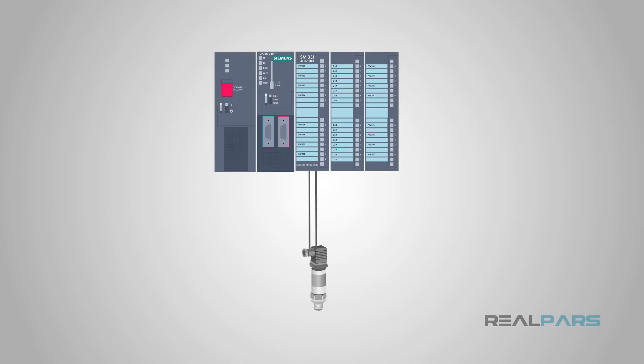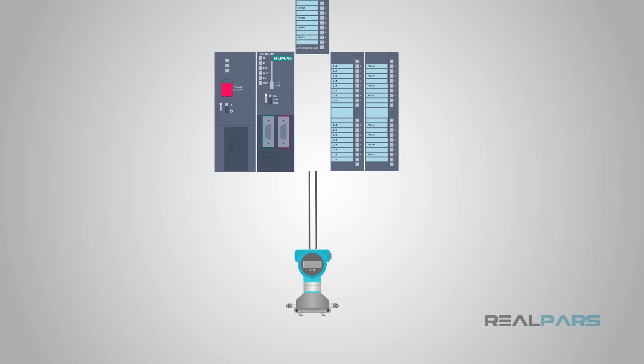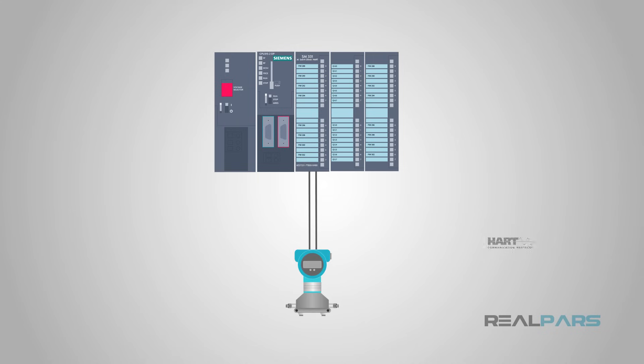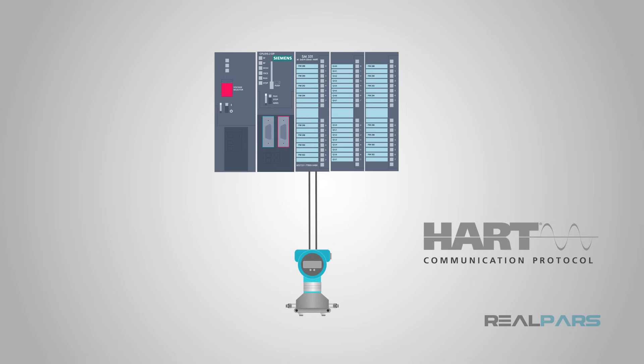HART communicates over a single pair of wires, so adding HART to an existing 4 to 20 milliamp sensor loop requires no wiring modification.